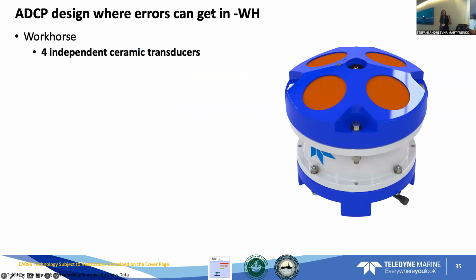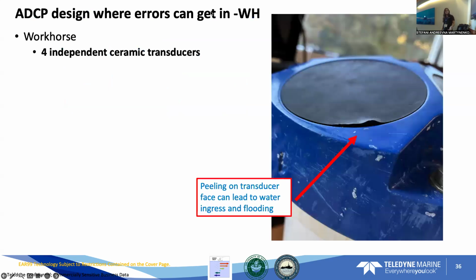So we now have a piston array, so it has 4 separate beams, unlike that phased array. And with the piston arrays, you can get some of this peeling on the transducer, and your signal will at first look fine, but as soon as we see any peeling like that, you're going to want to remove that system because that can lead to water ingress through the ceramics into the electronics. So that is a common mode of flooding and failure in the workhorses that you need to be aware of.